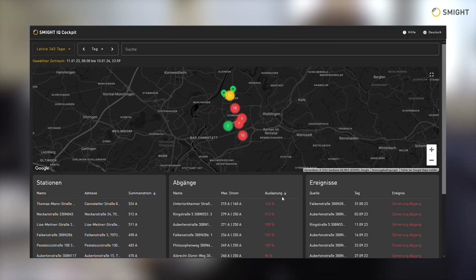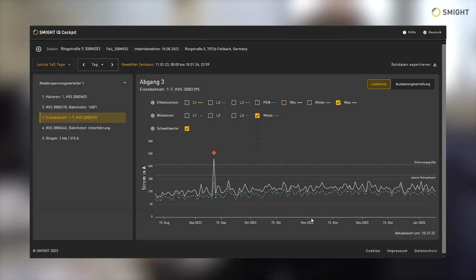On 11/09/2023, we received an email with a warning message that there was a fuse threshold violation on this substation. I now go there and see here that we have exceeded the fuse rating once.